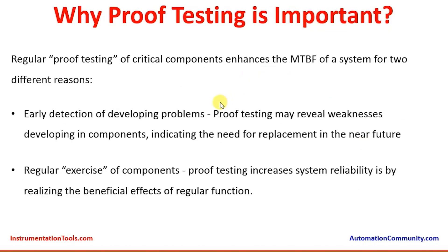Regular proof testing of critical components enhances the Mean Time Between Failures (MTBF) of a system for two different reasons. The first is early detection of developing problems — proof testing may reveal weaknesses developing in components, indicating the need for replacement in the near future. This supports maintenance teams to take early action to replace or repair the instrument as required.